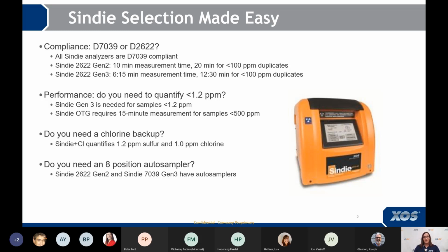The next thing you want to think about is performance. How low do you need to go? If you need to quantify less than 1.2 ppm, we really recommend the Sindie Generation 3. Okay. Another note on measurement. The Sindie OTG is available. It is our lower cost option, but do note that it requires a 15-minute measurement time for samples less than 500 ppm if you want to consistently comply with the D7039 method. Next, you want to think about some other things like, do you need a chlorine backup? We do have a Sindie plus chlorine analyzer, which will quantify 1.2 ppm sulfur and 1 ppm chlorine. And then lastly, you can think about some optional accessories like an autosampler. We do have 2 models of Sindies that do come with autosamplers.